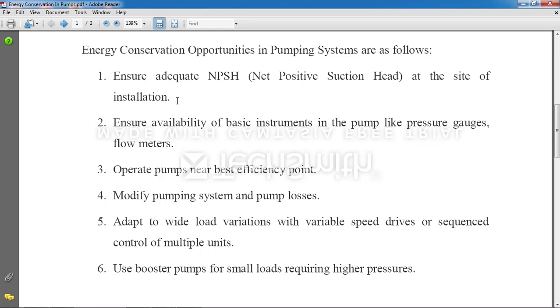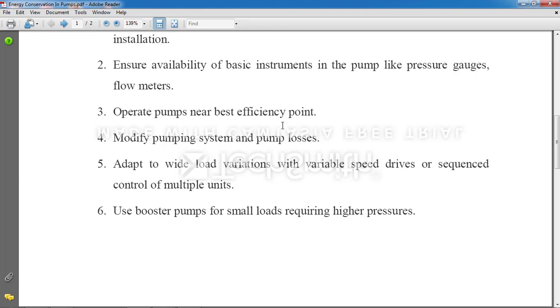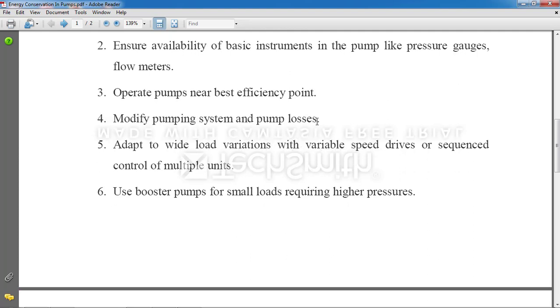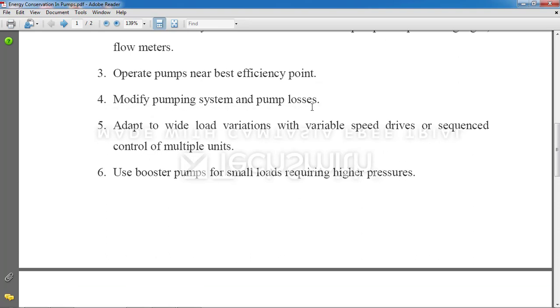Okay, that's why it is quite important, whenever you are installing a pump system, you should understand what is the requirement of the site. Point number 2, ensure availability of basic instrument in the pump like pressure gauge and flow meter. So that is quite important, because you have to fix the pressure. The pressure should be in a limited range, because whatever the pipe system you are using, the pipe should be able to sustain that pressure, otherwise the system will burst out. Next point, operate pump near best efficiency point. That is a quite obvious point, that whenever we are using something, we have to use it with the best efficiency.